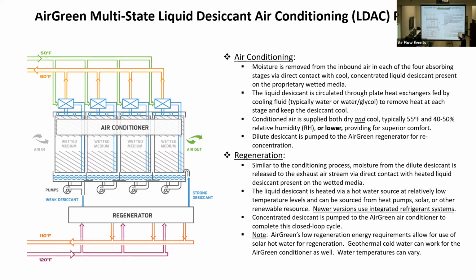So that, and then the regenerator, which, if I made this a full picture, would look exactly like the air conditioner. On the hydronic systems, we're using chilled water to cool the circulating desiccant inside the air conditioner, and we're using hot water on the regenerator. One thing that's different between us and solid desiccant systems is it's very low hot water energy requirements to regenerate. We can do that between 105 and 115. We don't have to go all the way up to the higher end. So if we're tied to, say, a heat pump, a water to water heat pump can run the whole thing. Yes. And that keeps our energy use low.